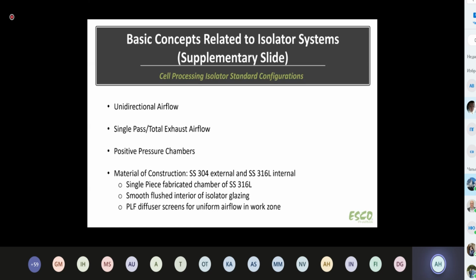We will have to see what is the situation on the clean room side. Okay. The chamber is normally positive. So unless you're handling a dangerous vaccine for cell therapy, most of the time our customers will be requiring positive pressure chambers. The pressure inside the isolator is positive. And in order to have good cleanability, all the insides will be SS316L and the outside will be SS304. Everything will be smooth and a single-piece chamber.